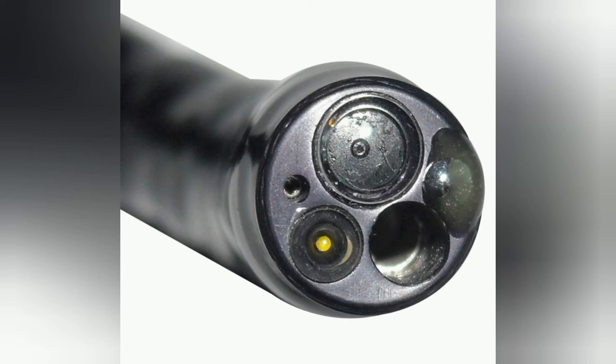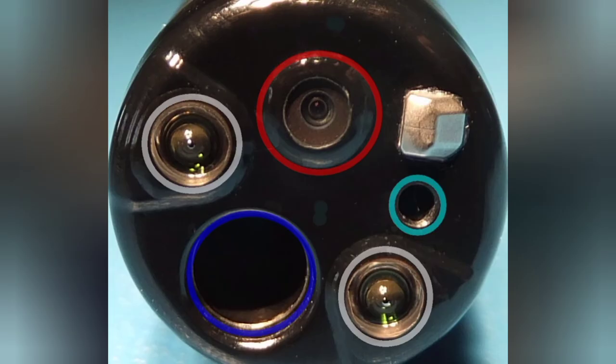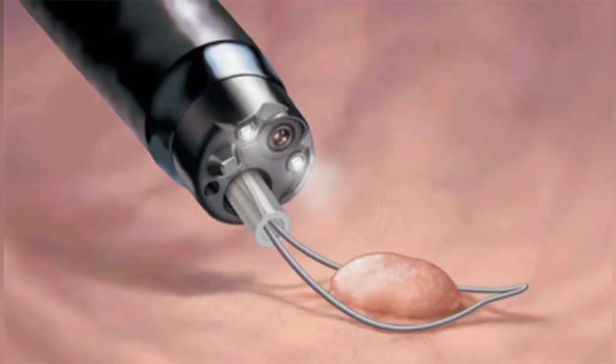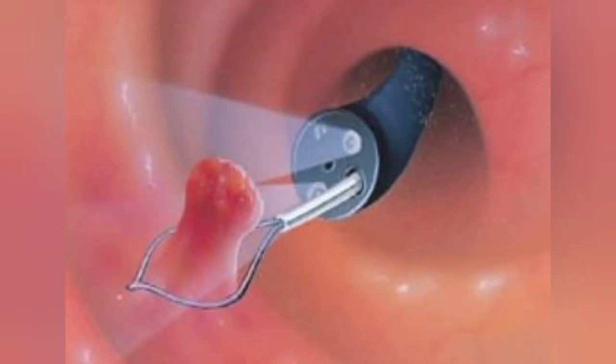Inside the tube of 10 mm diameter, flexible scopes enclose a water channel, light channel, camera lens, and air/water channel. If needed, an instrument channel is also enclosed inside the scope. All these components are fitted in very little space, so they are tiny — invisible to the naked eye — but work amazingly. Some flexible scopes contain a channel for tools used for biopsy, so a piece of defective tissue can be collected at the time of the procedure.